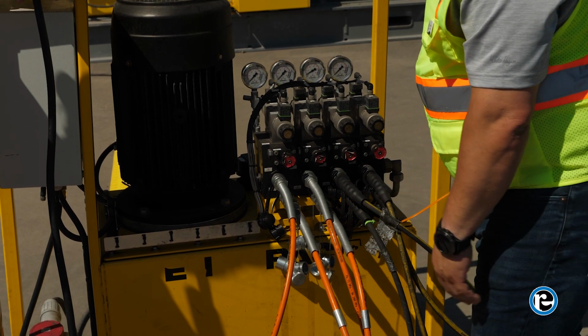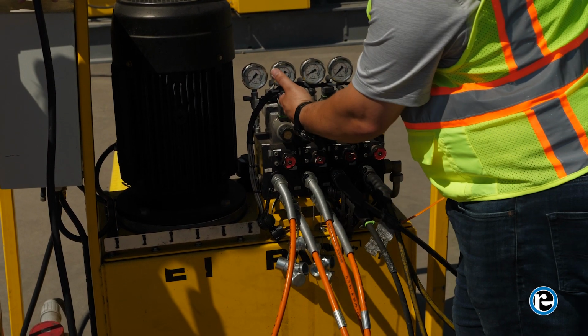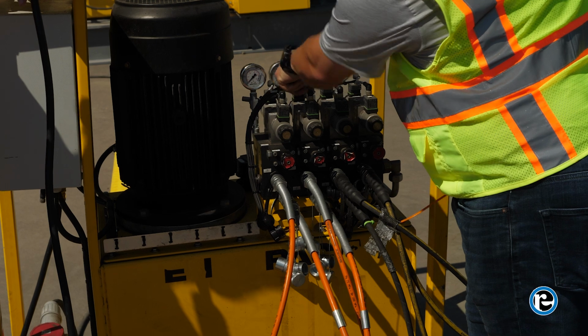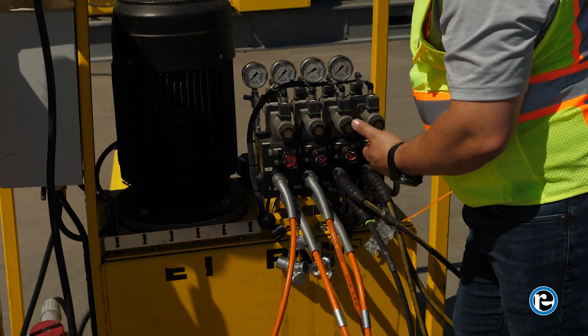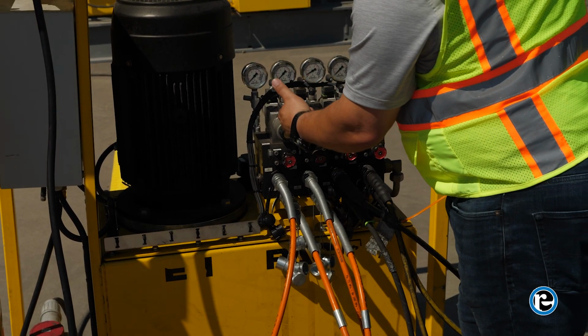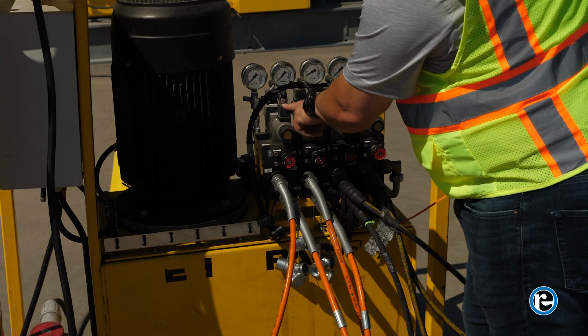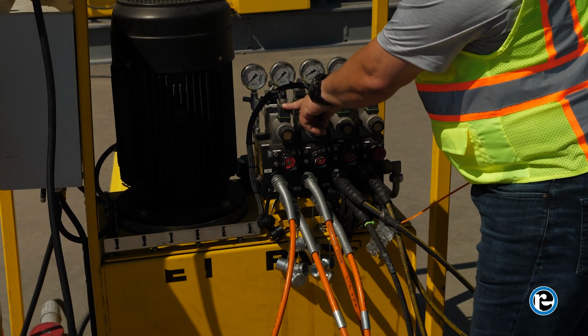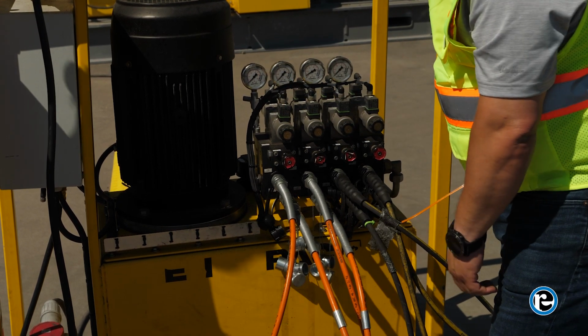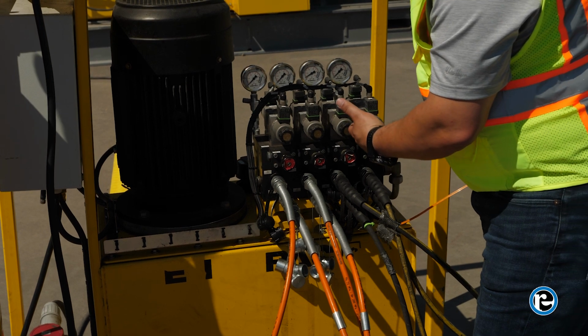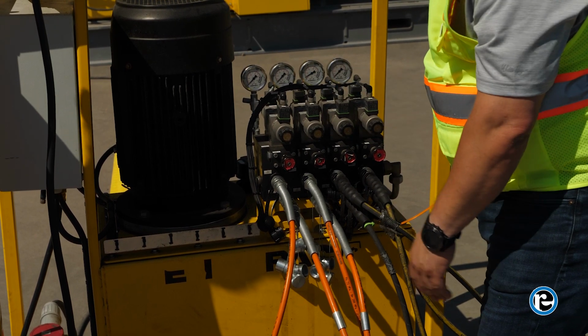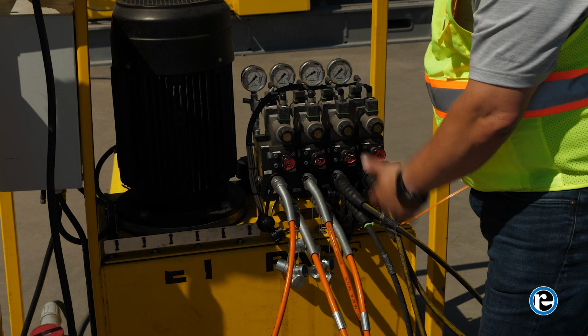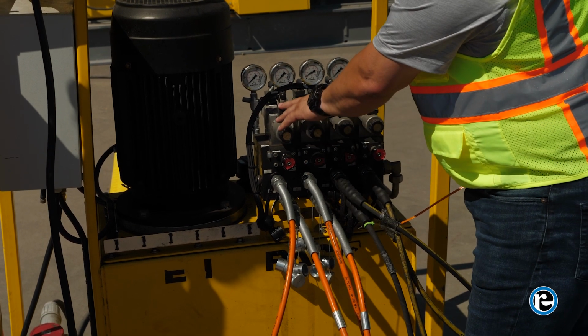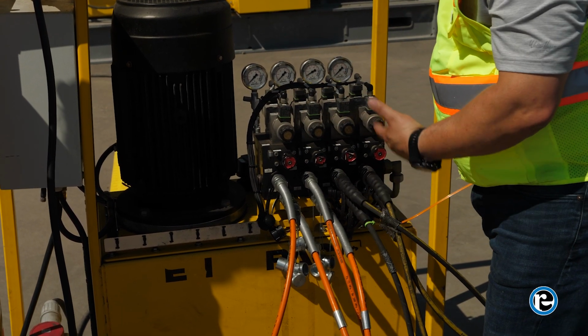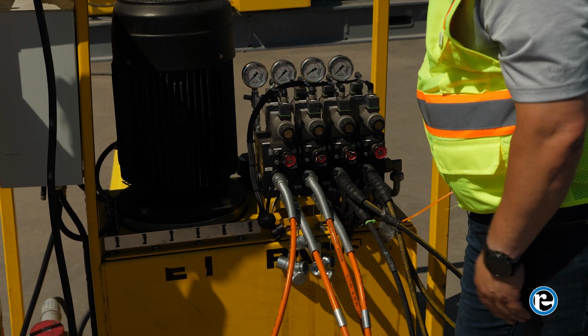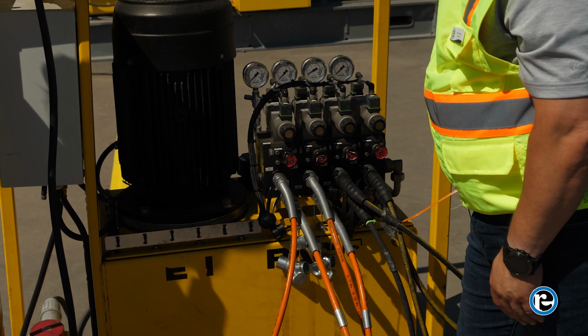The other thing, when you're using the pendant, if we're firing the valves, we'll have lights on the valves. When it's working properly, if I'm firing to extend the cylinder, I'll see this light up, and if I'm firing to retract the cylinder, I'll see that light up. So if something isn't working, for example maybe during shipment something electronic got jostled, we can check to see if we have an electrical issue, or maybe some other kind of issue, no flow, or dirt in a valve or something like that.